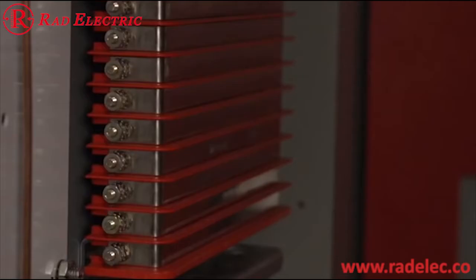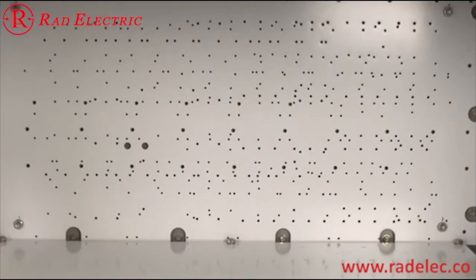When working around medium voltage equipment, it's critical that metal structures are grounded. On the left side of this cell is a ground bar. The bottom of the circuit breaker has a contact shoe that contacts with the ground as soon as you insert the circuit breaker into the cell. This is the secondary disconnect block. It has 16 contacts, which connect into the control circuitry and auxiliary interlocks on the circuit breaker. From this block, a wiring harness can be routed into the low voltage compartment. This equipment ground is used for grounding the controls and protective relays, as well as the switchgear structure.